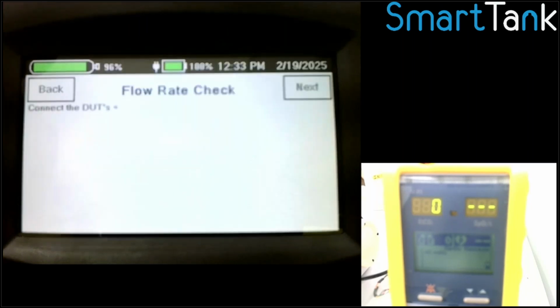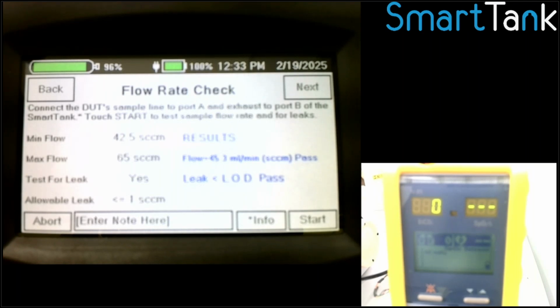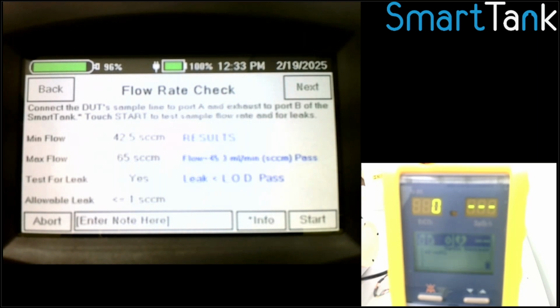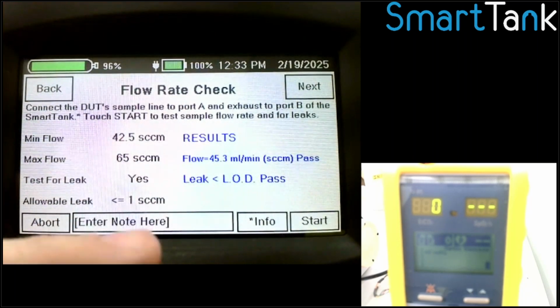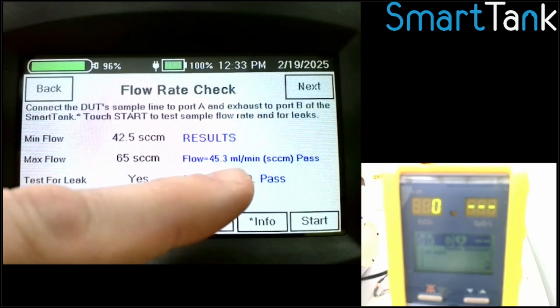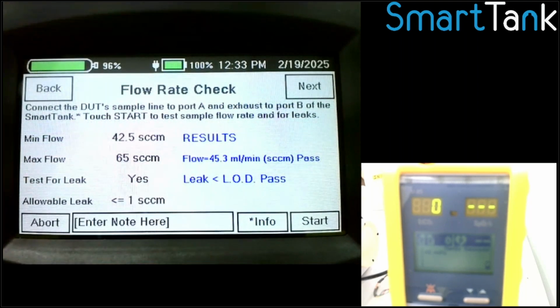And in this case, since I had that exhaust port hooked up, it's going to check for leaks using a faster leak checking method. So you'll see here it finished. Oh, let's see if I can get it to focus. There it goes. You're at about 45.3 milliliters a minute, so that passed, and the leak is less than our limit of detection. So again, that's that 0.5 milliliter a minute. So essentially, there's no leak that we could even detect with our sensitive flow meter.